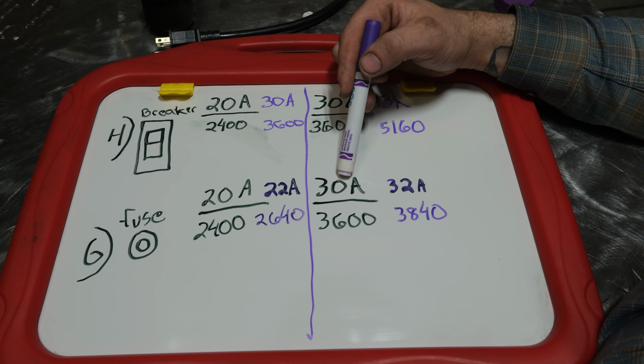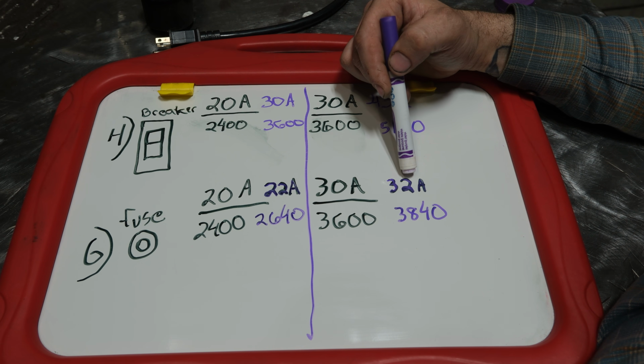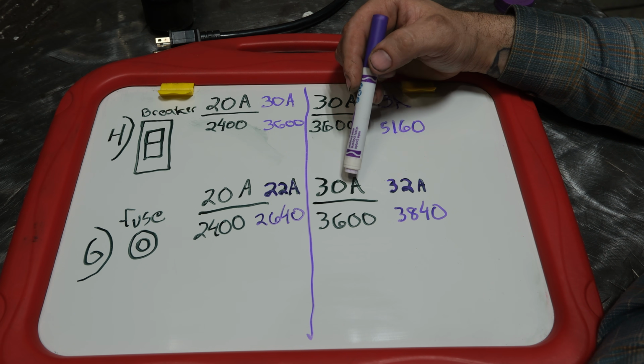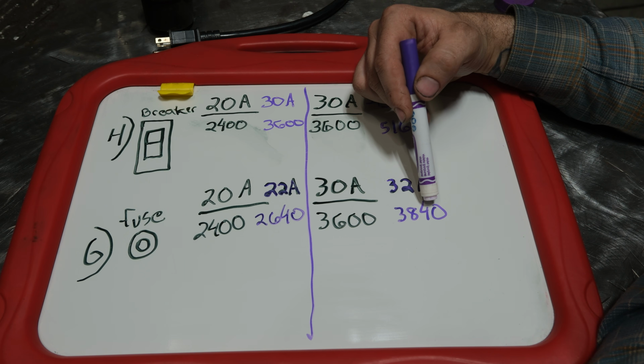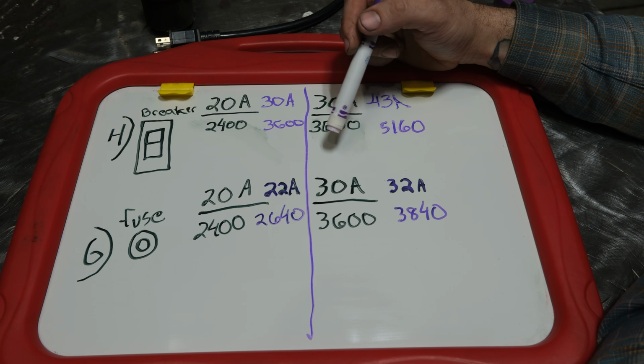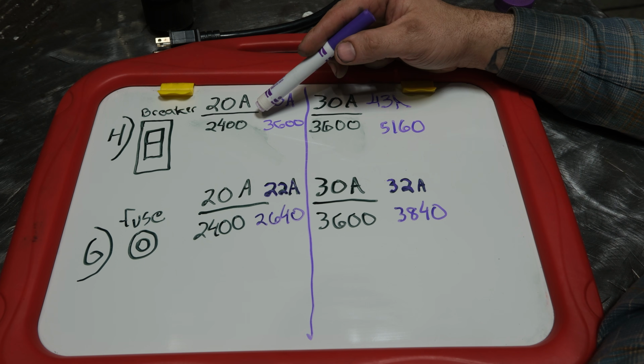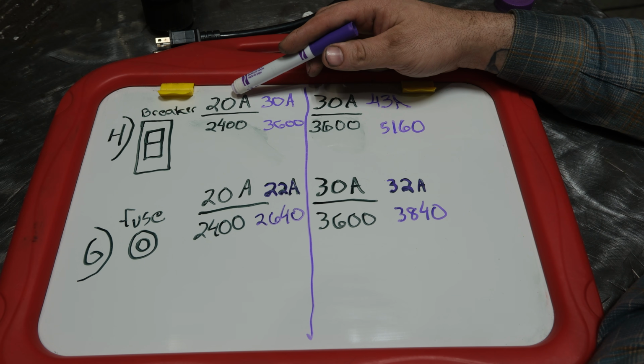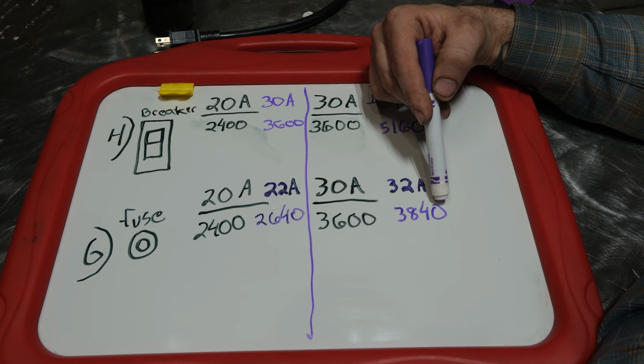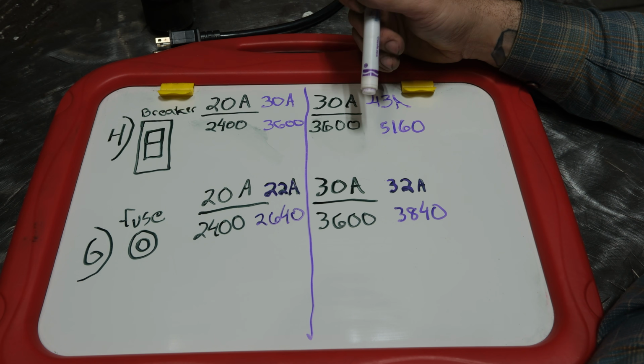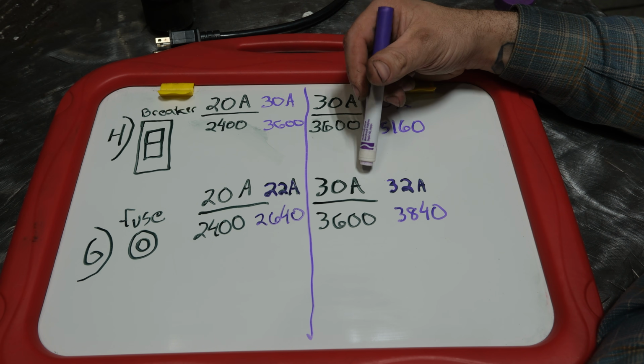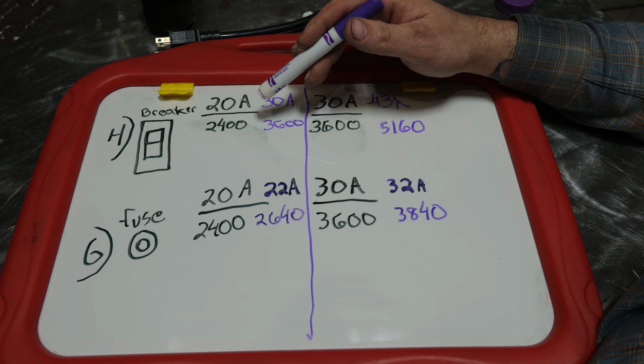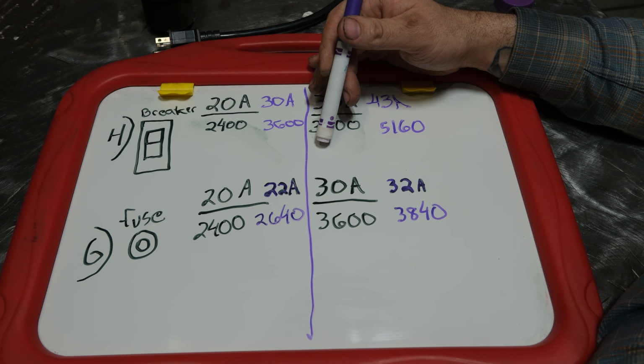And the same holds true on 30 amp. Same deal. 32 amps is about the most you're going to get through, which is barely any more wattage. And as a matter of fact, you can almost pull the same amount of wattage on your home 20 amp breaker that you could on a 30 amp breaker on your generator. And I don't make the rules, but this is just how it is. And this is only part of the problem that you're facing running on a generator.